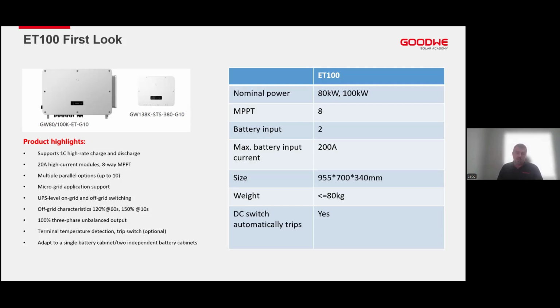Again, the unit is very compact with the separated STS design, and the weight is manageable for 2 or 3 guys to lift and install. And something else that is also unique, it will have an integrated DC switch that will automatically trip on certain conditions. In terms of major highlights, as I mentioned, 8 MPPTs with 20 amp input per MPPT. That will accommodate the 210 millimeter modules from 600 and 620 watt and upwards.